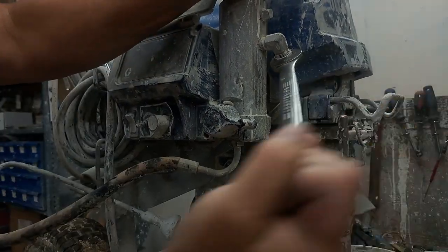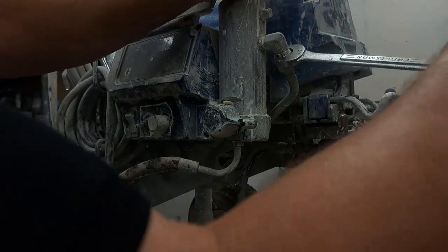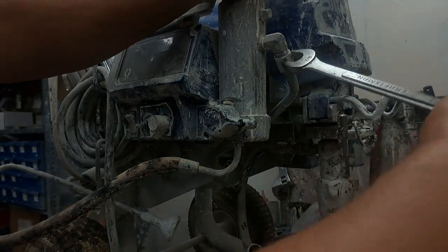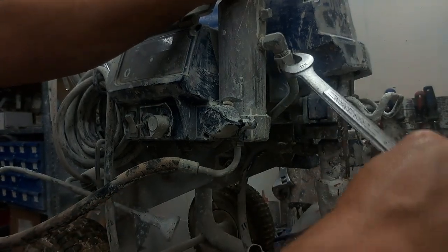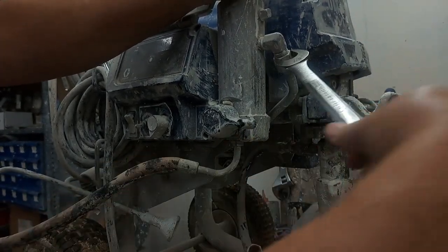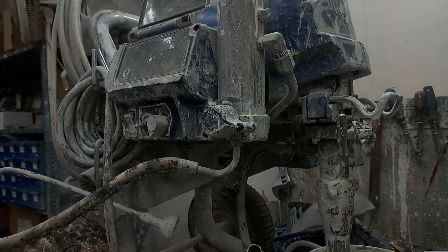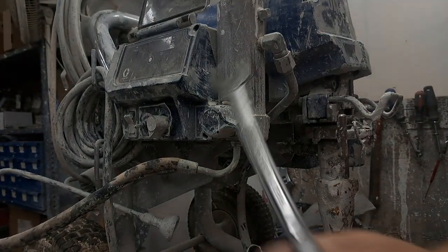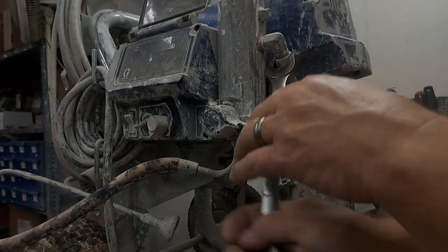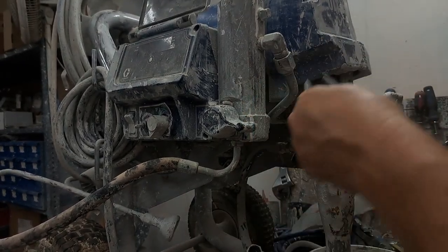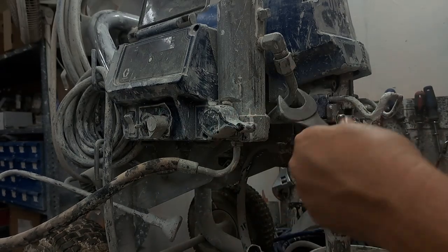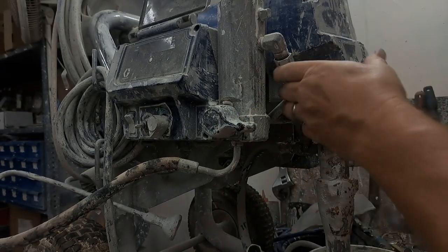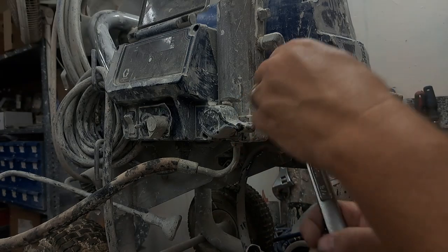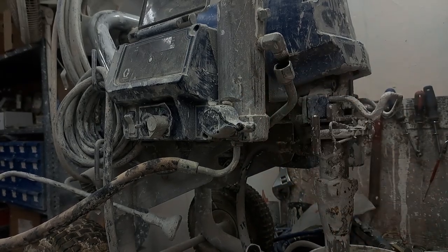I'm going tight. There we go. Sometimes when you tighten them up, just a tweak, they will loosen up. That's on a lot of bolts and everything else. But anyway, so the transducer actually measures the amount of pressure that you're achieving. Your potentiometer or pressure control sets the pressure that you want. Alright, now that's loose.